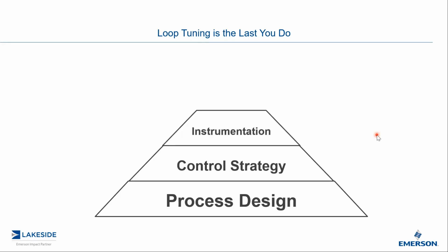Instrumentation. Obviously, on one side of the equation, you got to have the right instrument properly specified, installed, and maintained. So obviously, we have to make sure that when we design a process the instrumentation is properly installed. Don't install a mag meter, let's say, flanged to an elbow. That's not a good idea. Don't put your pH transmitter in another building, which I actually have seen. So make sure we design our instrumentation so we get the maximum value.